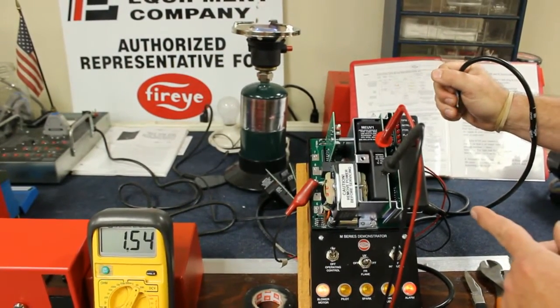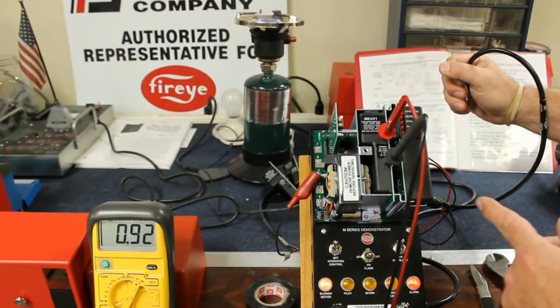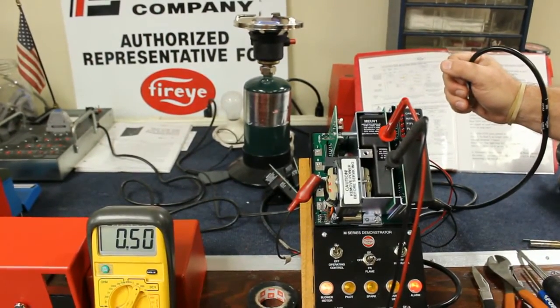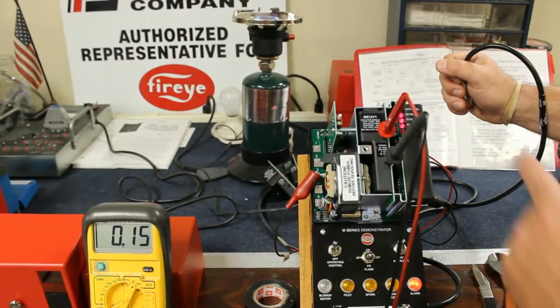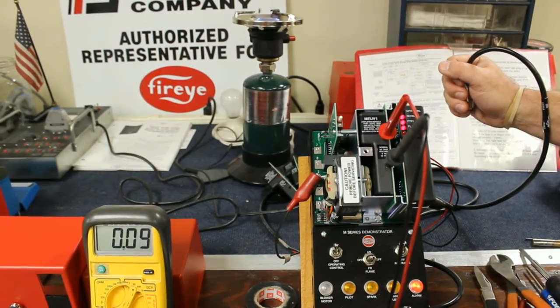Now if it were to see signal now without being in pilot trial for ignition, it would still head to lockout thinking it's seeing a false flame. And there we have it, it flashes a code telling us what went wrong.